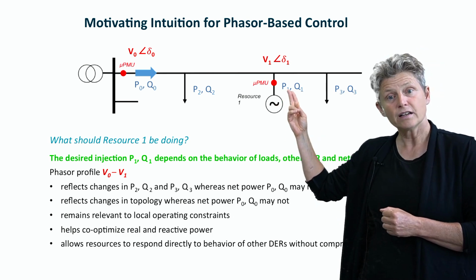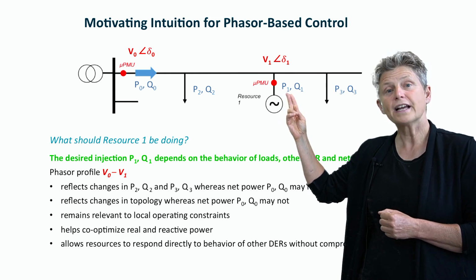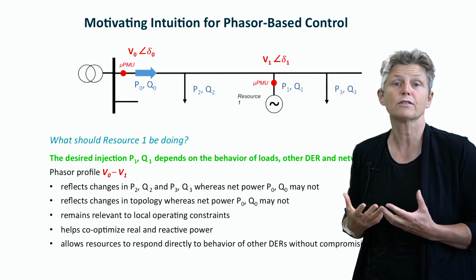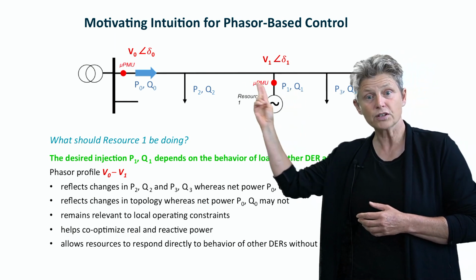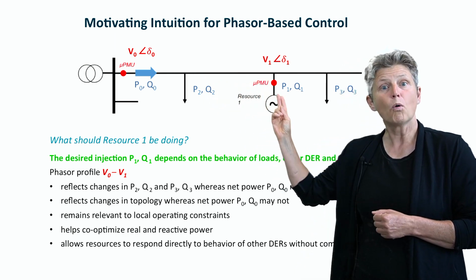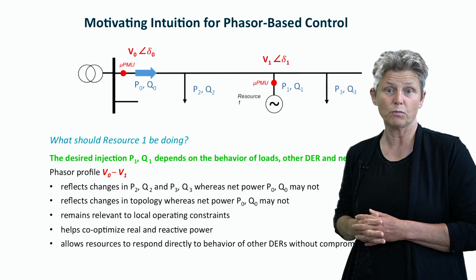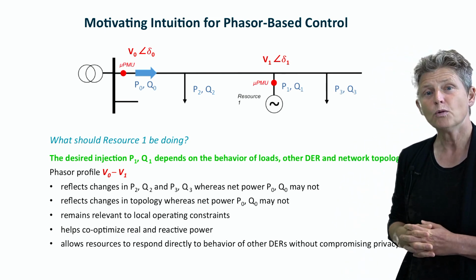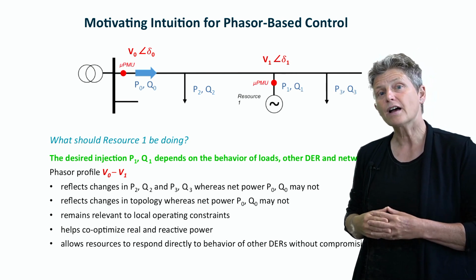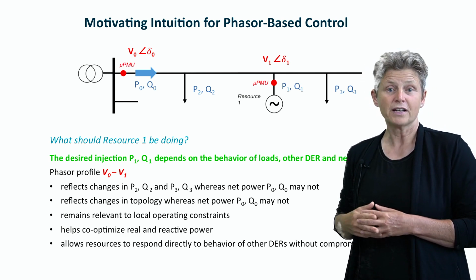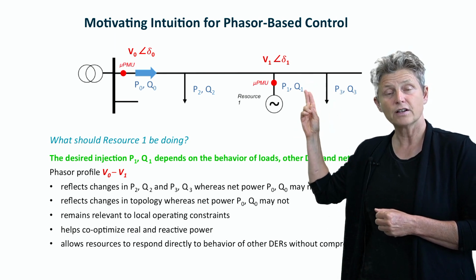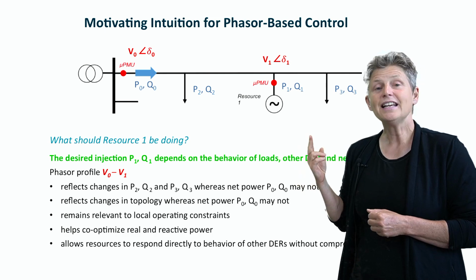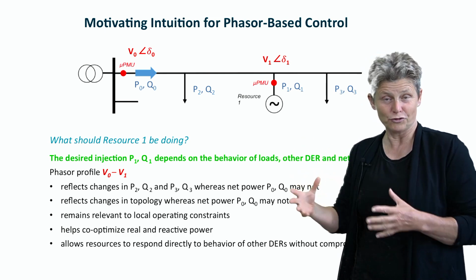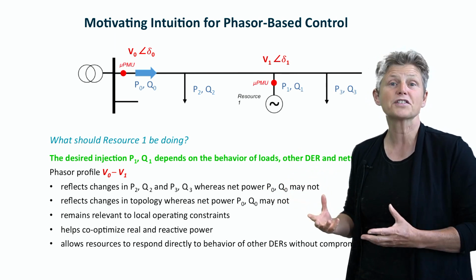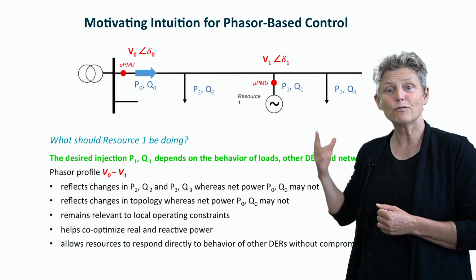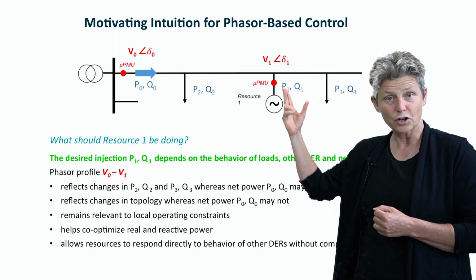If it's at the feeder end, maybe we care a lot and need to counteract that more aggressively. So by looking at the voltage phasor at a particular location, we're getting a really useful indication of how much strain or stress there is on the circuit, how close it is to overloading, or whether we're within the bounds of voltage we want to manage. At the same time, we're getting that locational information without having to compromise our neighbor's privacy. We don't need to measure branch currents at any of our neighbors to know approximately, from a geographic standpoint, where this load is occurring and where we can best compensate for it.